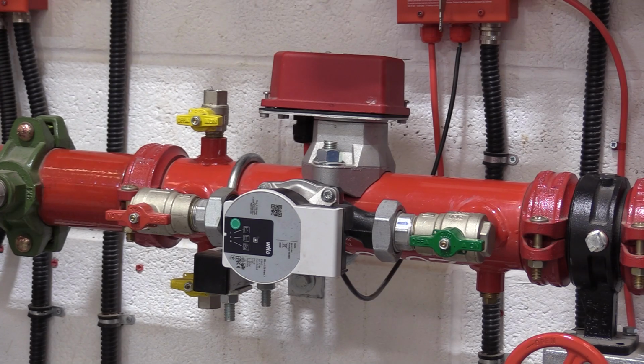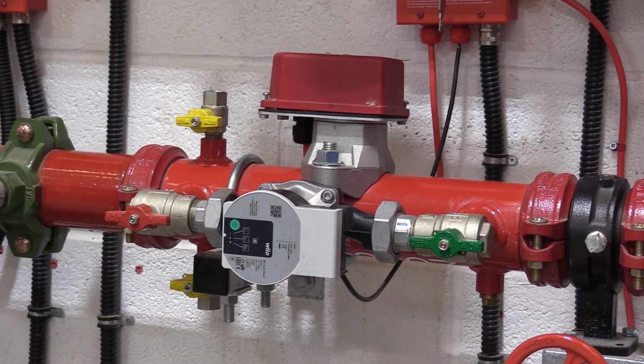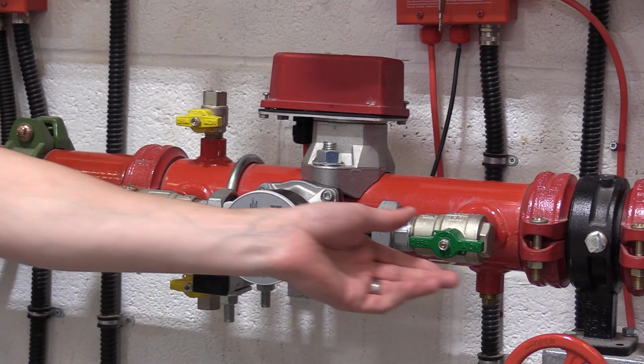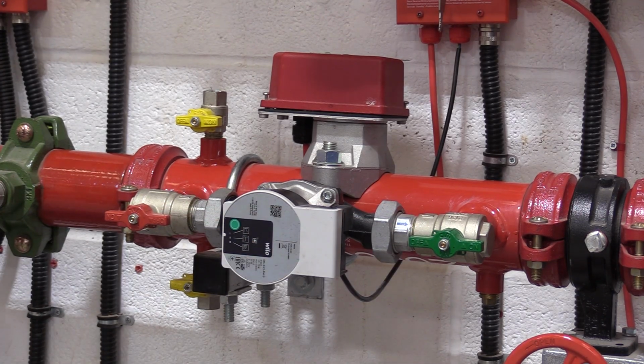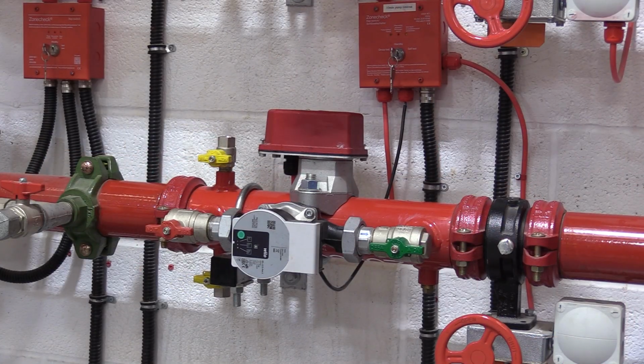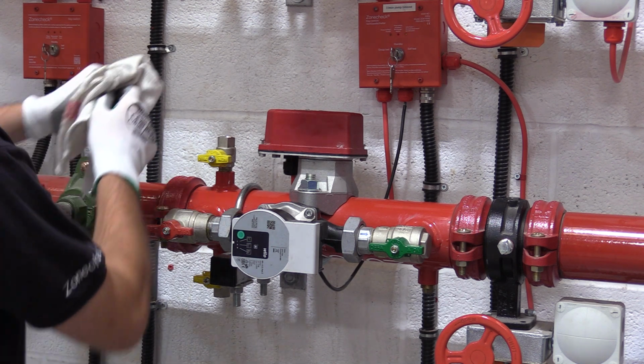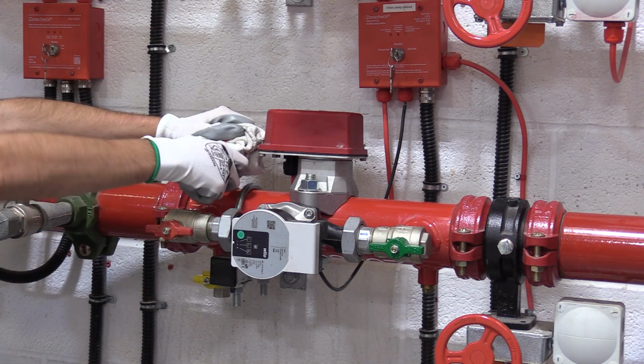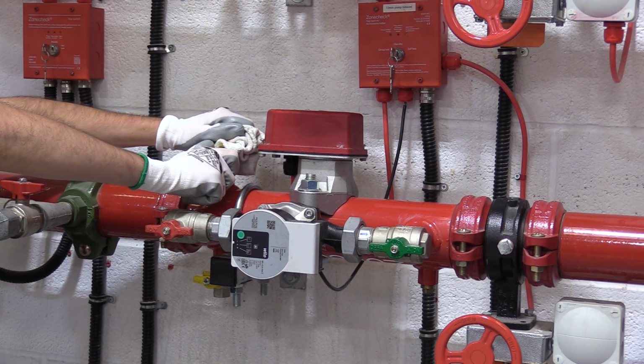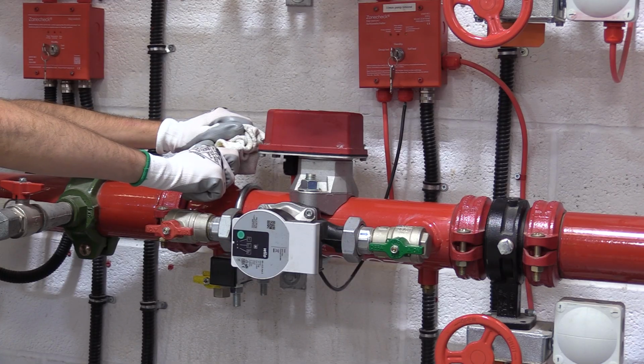The Zonecheck pump has two isolation valves either side, one red and one green. These should both be in the open position. Zonecheck cannot be run without water in the pipework. If you are unsure if water is present, you can crack open the drain or vent valve with a cloth or bucket ready.